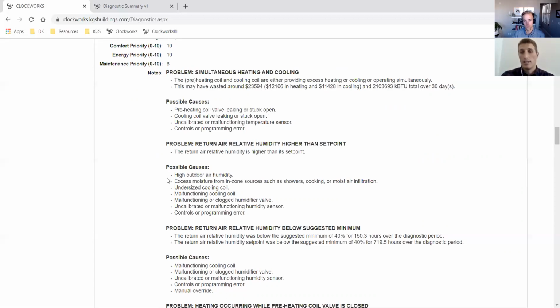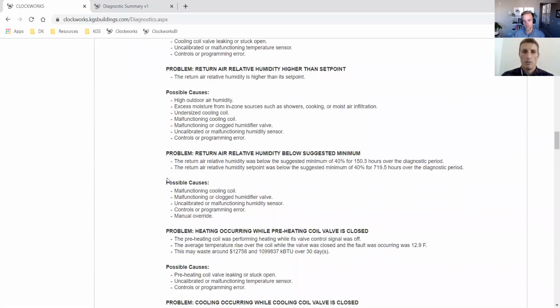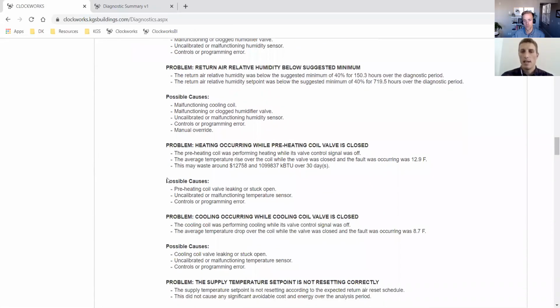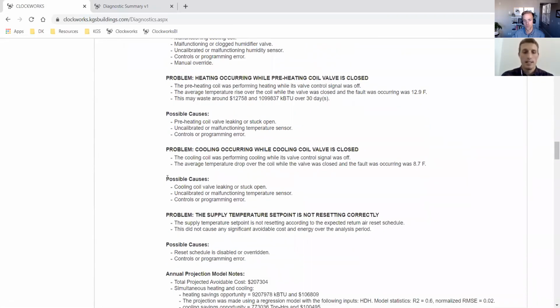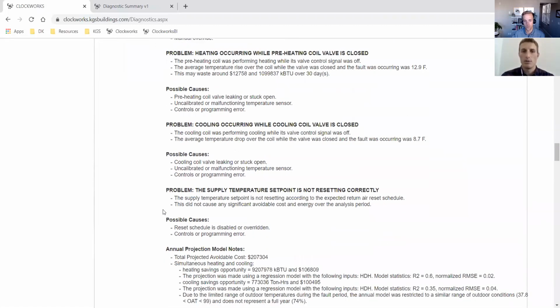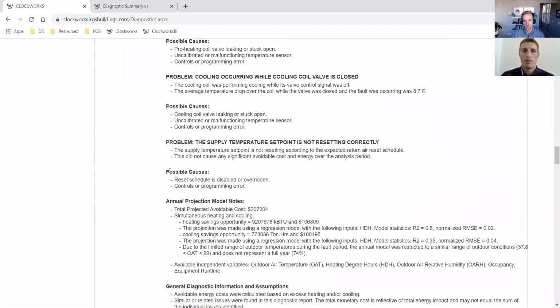We also detect things that aren't necessarily related to that issue, but could be an opportunity to investigate while you're fixing that issue on the air handling unit. So if I'm going to go fix that valve, I might also want to know that my supply temperature set point is not currently resetting. Is this impacting comfort? Not at all, but it is wasting energy. And while you're there, you should investigate the control sequence—see if there's an override in place that you can remove.